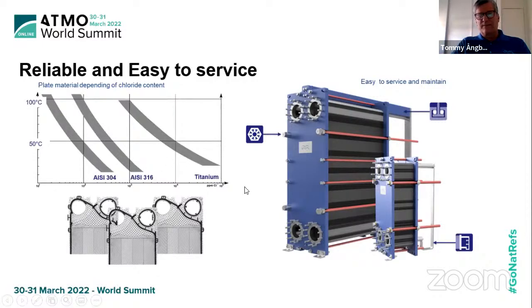But these are standards. And our heat exchangers, when you clamp them together, as you saw in the film, it's important that you can open them easily, and we always have ball bearing rings so that it's easy to open and close, to do the service, to clean if some dirt enters and so on. I mean, the cold side is really sensitive on the heat pump, because some liquids are more dirty than others.